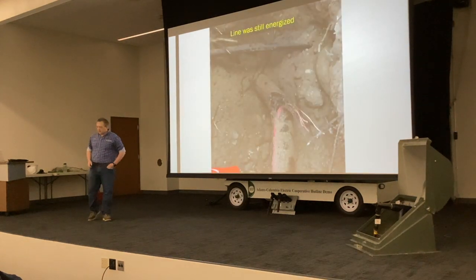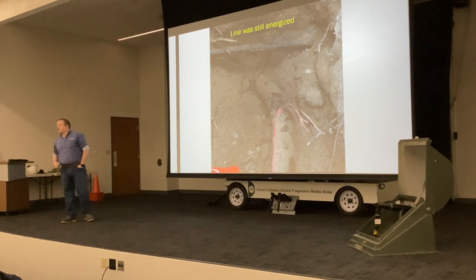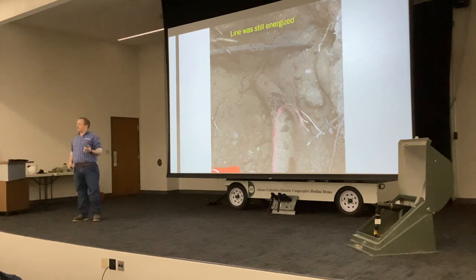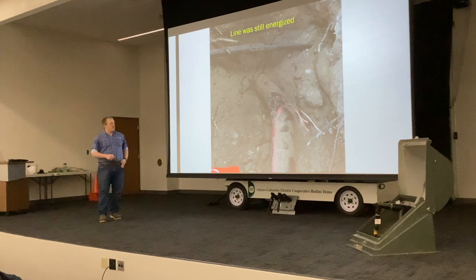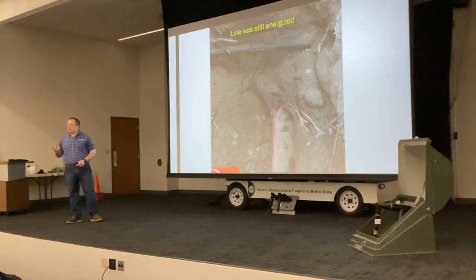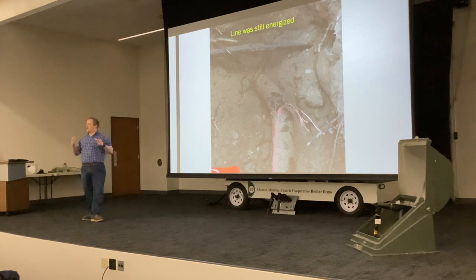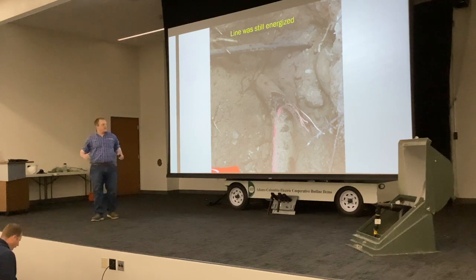If you remember when I talked about the primary, phase, and neutral earlier, underground has the same thing, but they're actually tied together in the same cable. If you're doing any digging and you skin the jacket, there's a chance that you're going to pull up these copper wires. These are our concentric neutral. We take a lot of small copper wires, wound around it, and then when we get to a termination, we bunch them all together, twist it together, and it looks like a nice copper wire.